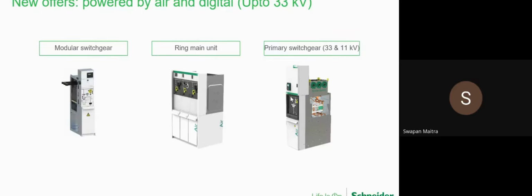These are called primary switchgears. This is a ring main unit. Here, in this case, this is a single unit of panel, and another panel can be added on the right side, left side. So there can be a series of panels, 10 panels, 12 panels, 15 panels, any combination. And every panel has a separate bus bar chamber and a separate breaker chamber. This is the mechanism. I'm just telling you to understand what the products are, so you become familiar with the products where these 33 kV equipments are there.